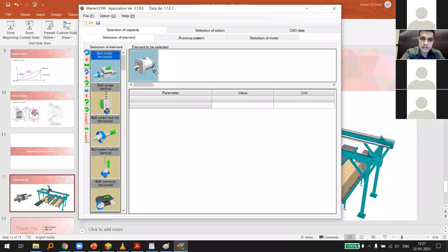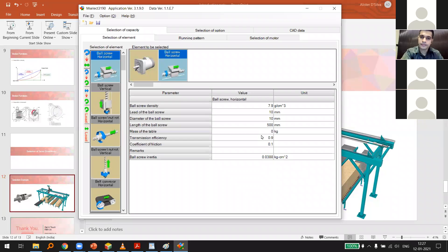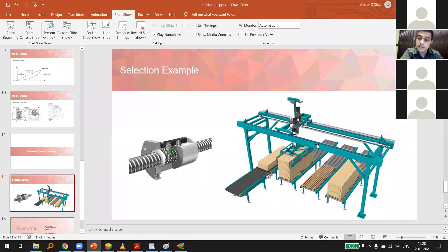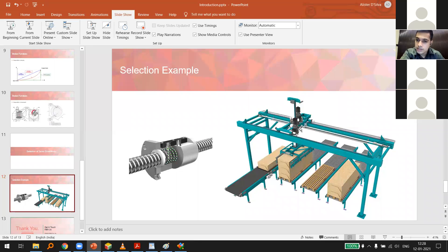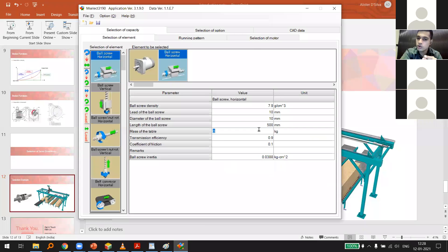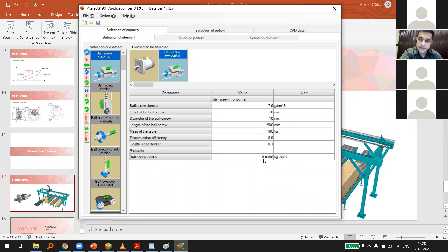Setting the speed curve: move 300 mm forward with 0.1s acceleration and 0.1s deceleration, then return to zero position in 1 second with the same ramp times. The software automatically calculates the required RPM based on the ball screw parameters and distance to travel. Then go to motor selection.